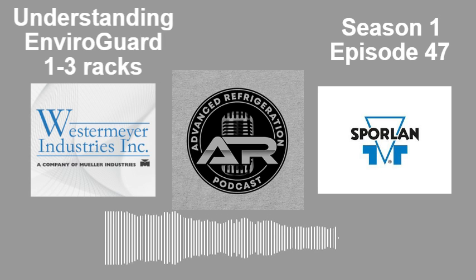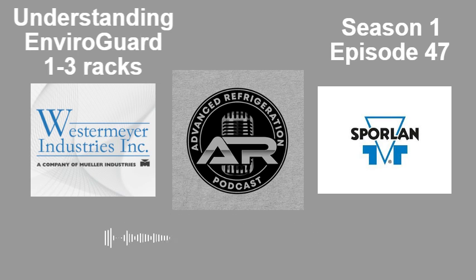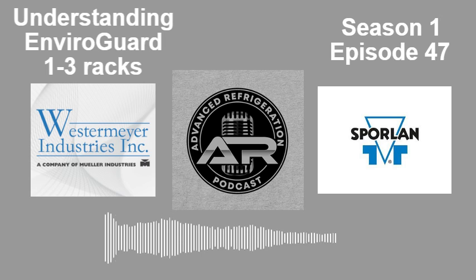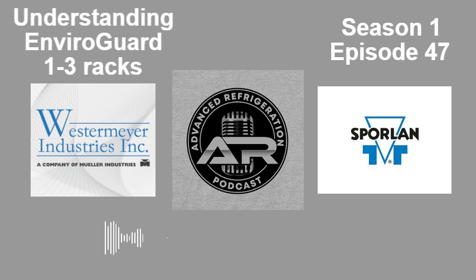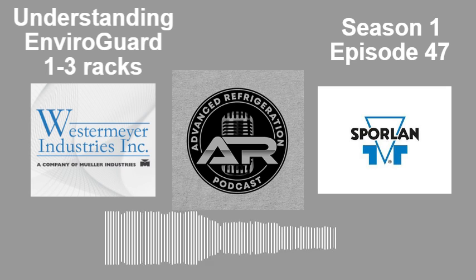efficient. You'd be surprised. We did 2 or 3 of them up here with my floating head, and then we put digitals. I converted the 3Ds to digital 3Ds. Those racks never ran better. We had hardly any calls on them in the wintertime. Yeah, they just run great. No short cycling. I mean, no stall outs in the winter when it's super cold, when the compressors become too big. They just ran amazing.